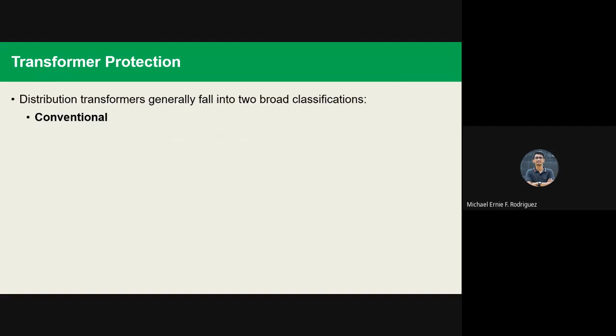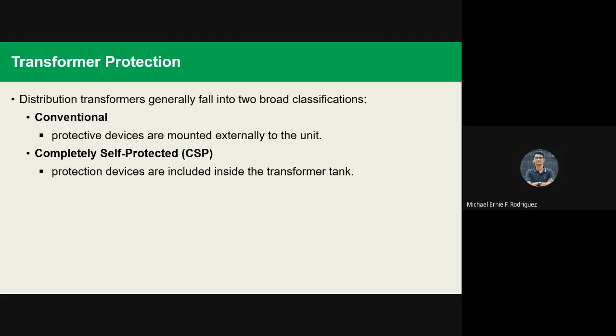Conventional protective devices are mounted externally to the unit. And we have the completely self-protected, or CSP, transformers, where protection devices are included inside the transformer tank. So protection is also provided against overload or failure and from voltage surges.